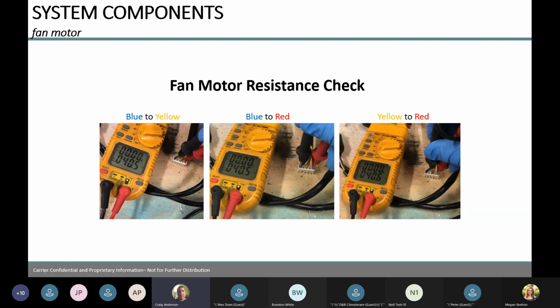So motor resistance, same as our compressors. We're checking them all, blue to yellow, blue to red, yellow to red. Same as everything else. We're looking at a resistance that's in the same parameters, nothing that's way out of scope when we're checking that as well.